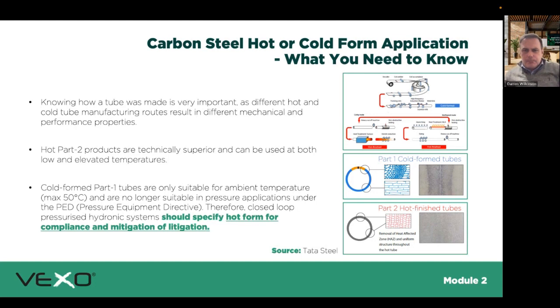Carbon steel, whether it's hot or cold form application—in a nutshell, when you're specifying the materials the system's designed for, if you're specifying carbon steel, there is a British and an EN standard in terms of its application. Just know that if you're using cold form, which comes more competitively than hot form, it also carries risks if you don't apply it correctly to the right sorts of systems.